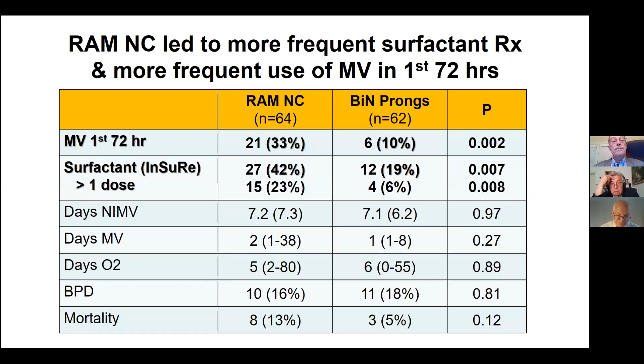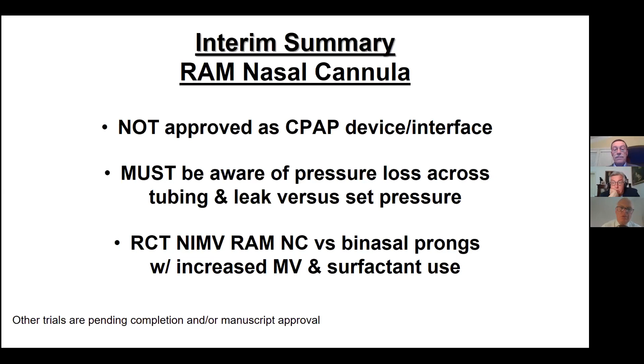You must be aware that if you are using this interface, there is a significant pressure loss across the tubing. Some of that is due to the tubing itself and the resistance of the system. Some of it is due to leak around the cannula because it's not supposed to be occlusive. And if you increase flow in an effort to increase pressure delivery, you will probably have less pressure delivered because of the effect of turbulence on the system. There are some design changes being developed by this manufacturer, and so perhaps this will all change over the next 5 years, but at this point in time, this is where we are.